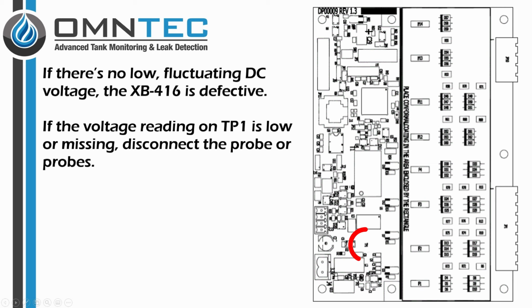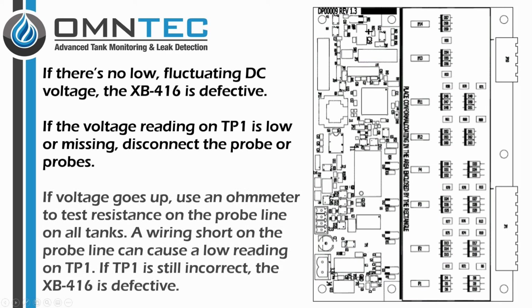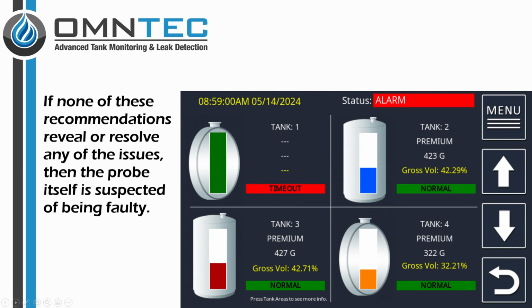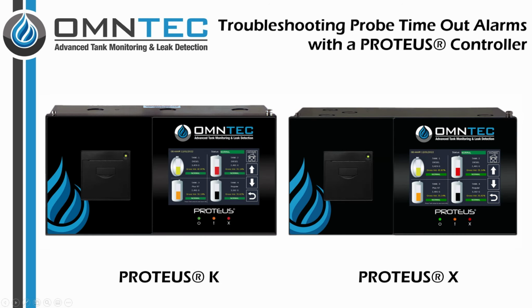If the voltage reading on TP1 is low or missing, disconnect the probe or probes. If voltage goes up, use an ohm meter to test resistance on the probe line on all tanks. A wiring short on the probe line can cause a low reading on TP1. If TP1 is still incorrect, the XB416 is defective. If none of these recommendations reveal or resolve any of the issues, then the probe itself is suspected of being faulty. This completes the process of troubleshooting probe timeout alarm issues on a Proteus ATG controller.